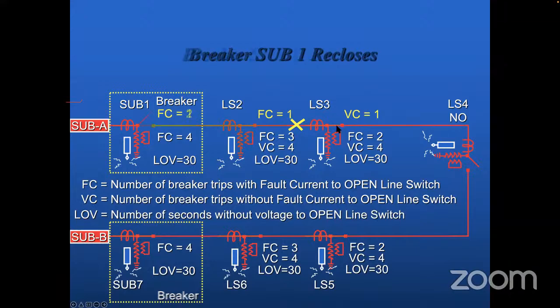So again it will open up. Now what will happen? Fault count becomes equal to 2 here, and fault count equal to 2 here, and the voltage count - that is, the number of breaker trips without fault current to open the line - that is VC equal to 2 now here. There is no VC here because this agent is still seeing the fault current. So FC becomes 2 here. You still have the fault here.